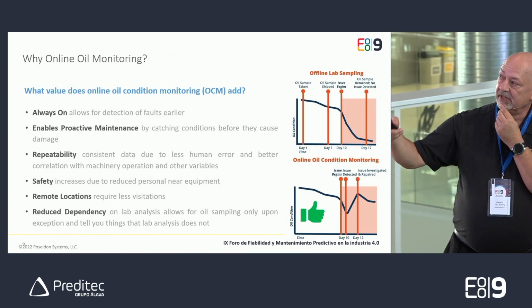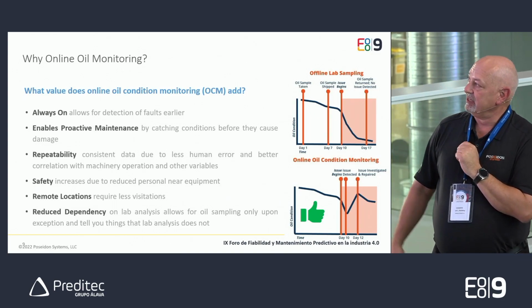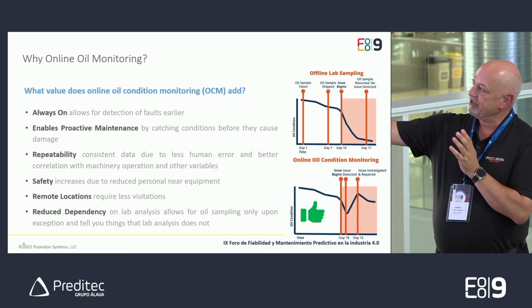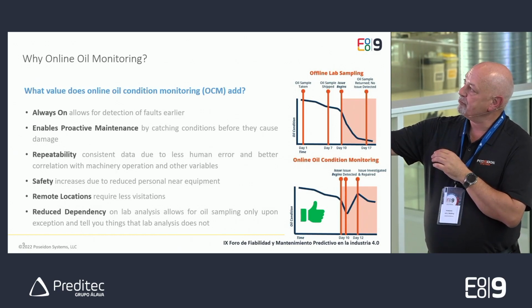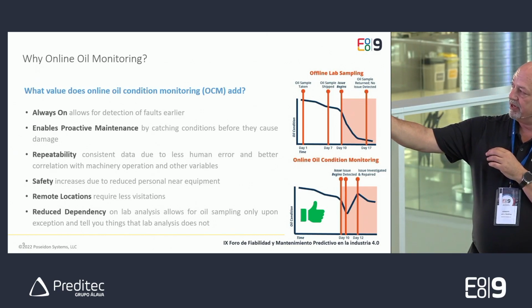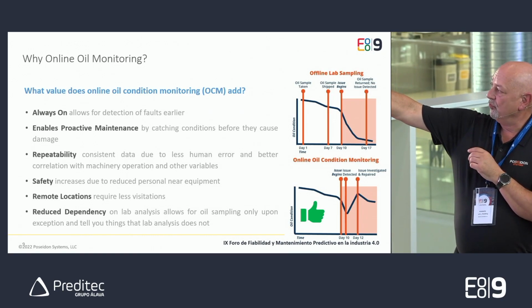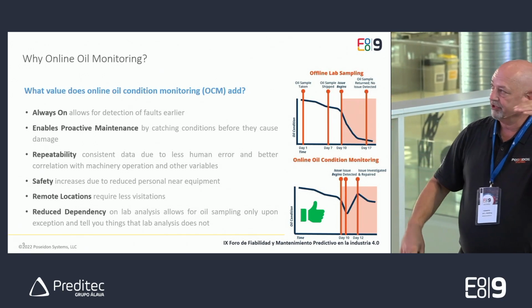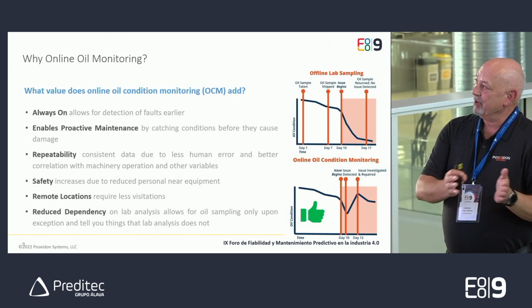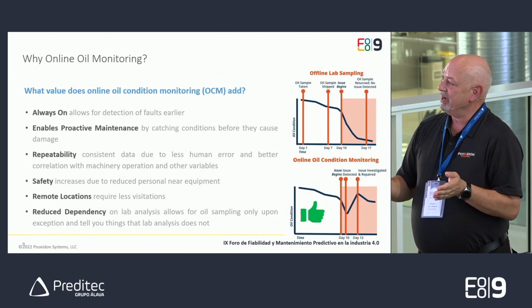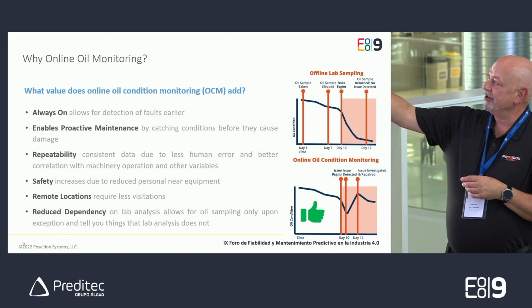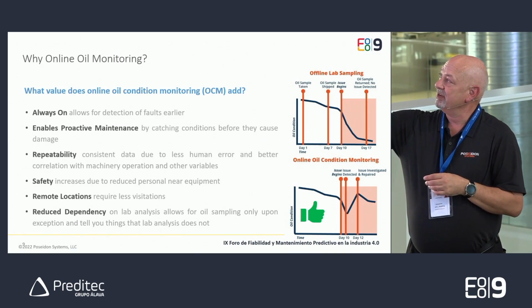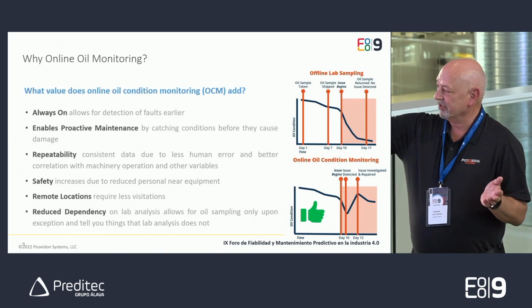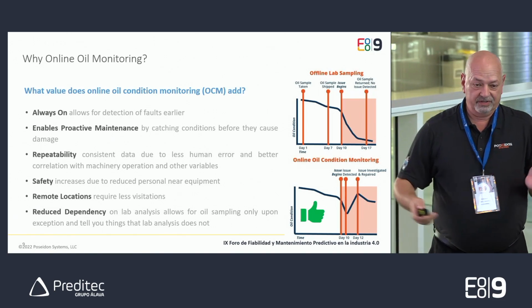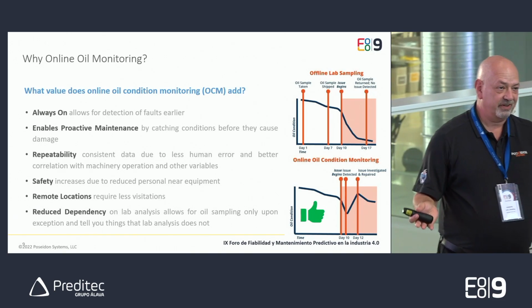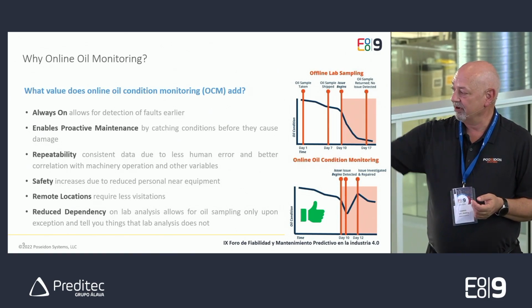So here's an example of why online oil monitoring. And over here, there's a couple of charts that show a typical situation where an oil sample is taken, and the line is showing the overall oil condition degrading over time. The sample gets shipped, the results come back. In this scenario, an issue begins on day 10. The oil sample comes, now this is unrealistically long, but 2 weeks later, the results of the oil analysis come back, so sample's good. Meanwhile, a problem has occurred.